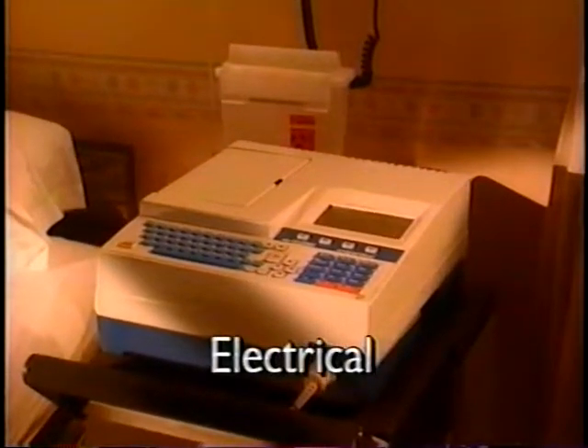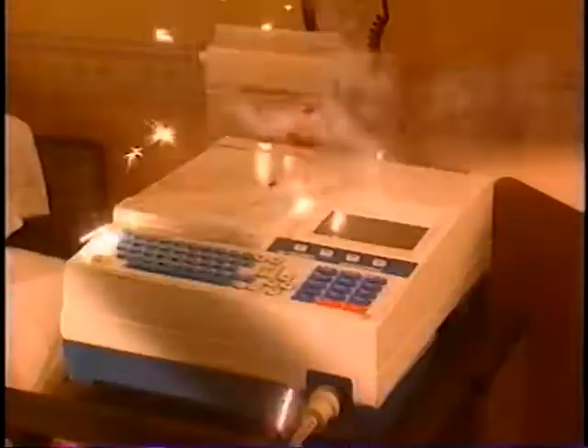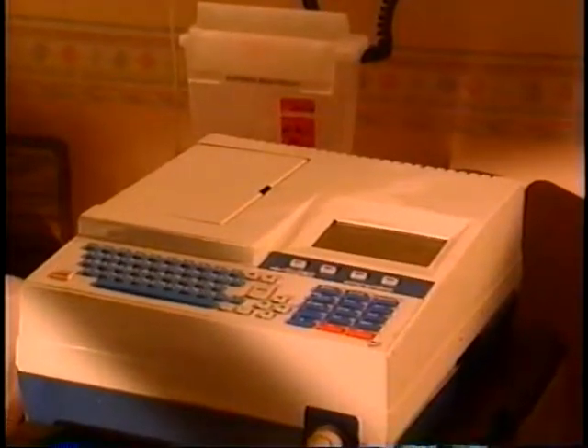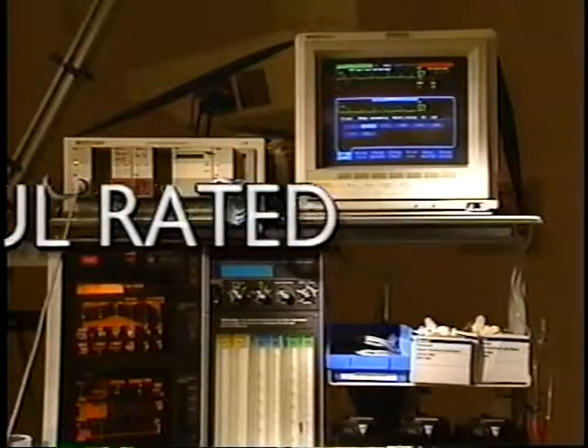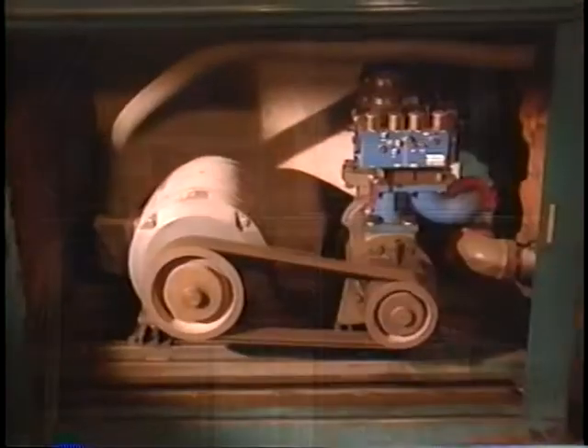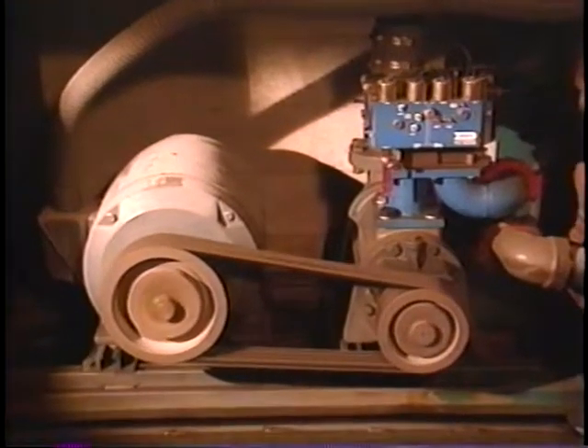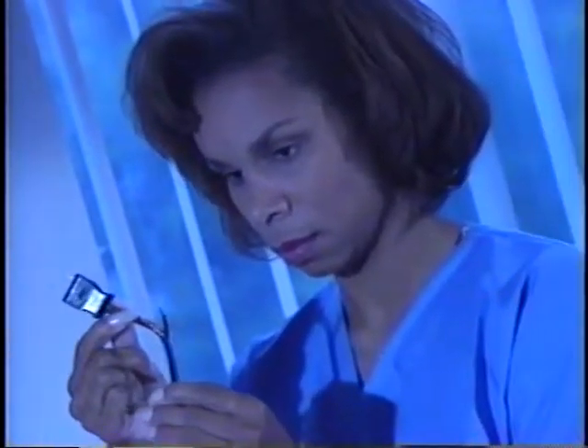Electrical fires are the most common fires in healthcare, so their prevention is your objective. Make sure that only UL-rated electrical equipment is used, and that all electrical equipment and motors are kept clean and maintained properly. Report old or worn wiring and broken or damaged fittings on equipment to the appropriate person. Never overburden electrical outlets or piggyback electrical cords. Extension cords should not exceed 6 feet and should not run under carpeting or be tacked to the wall.